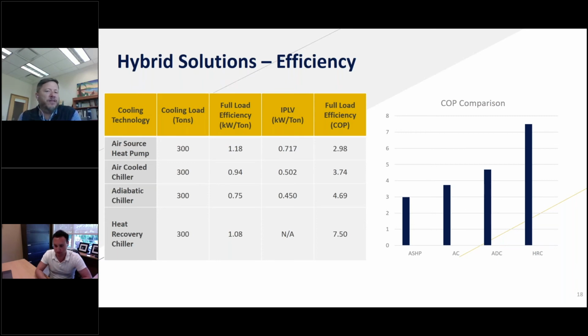And so you can see we get 30% more at full load. We're 30% more efficient, and we're approaching 40% more efficient at part loads, whether we go to an air-cooled package chiller or an adiabatic, right? So that 0.75 kW per ton full load and a 0.45 IPLV, if you start comparing that adiabatic chiller system to a water-cooled chiller with a cooling tower and condenser water pumps, that's really where you're at there as well.